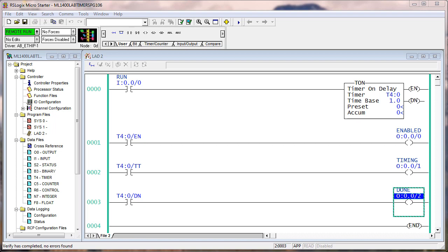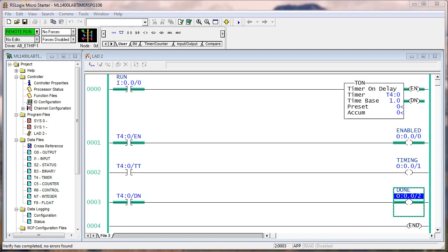I had you put in a preset of zero for a particular reason. While watching the accum field in the control bits, switch input zero to the on state. I flipped it on and the manual asked: did the accumulate increase above zero? The answer is no, because there was no preset. The instant that you enabled the timer data type it saw that the accumulate was equal to the preset — zero equals zero — therefore it was done. So the preset equaled the accumulate at the enable.